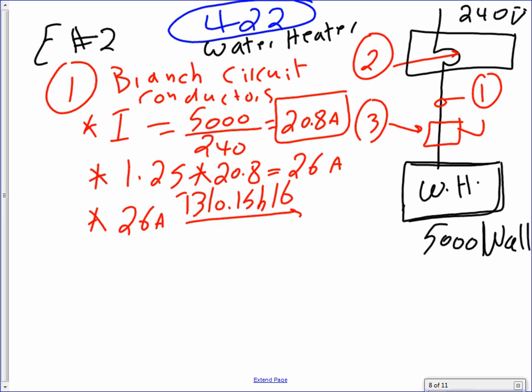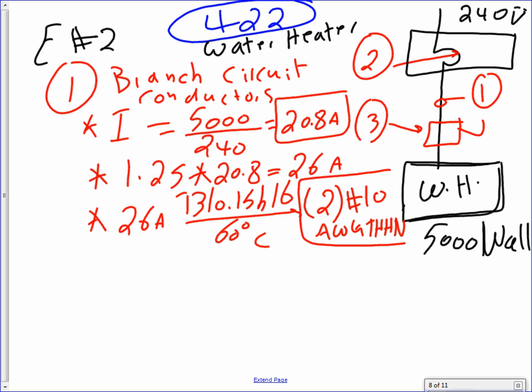310.15(B)(16) under the 60-degree column because it's not a motor. And that will get you two conductors, number 10 AWG THHN. So that we have two conductors.